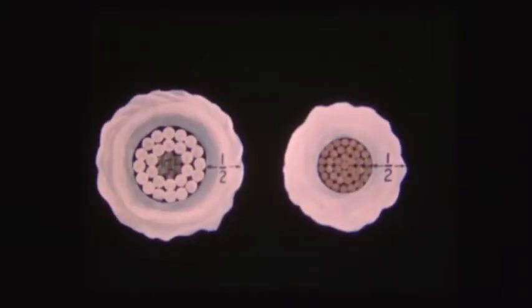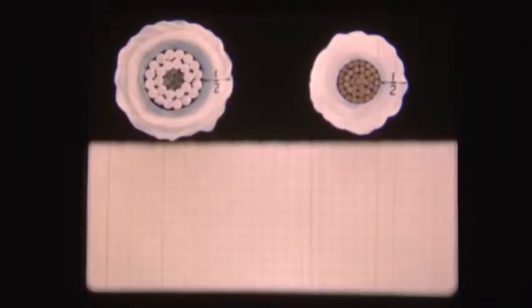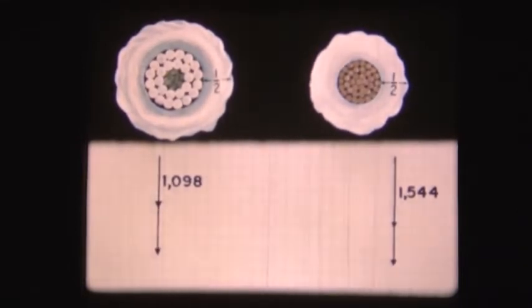Actually, the choice of conductor material isn't quite that simple. We have to consider such things as the added weight of ice, a half-inch coating throughout most of the Pacific Northwest, and up to a full inch or more where winters are unusually severe. Then, there is the added force of wind, which can reach velocities as high as 100 miles per hour in some localities. Let's follow through with the same examples and see how the design engineer uses vector diagrams in making a choice of materials. First, to the weight of a thousand feet of bare conductor, we must add the corresponding weight of a half-inch coating of radial ice, or 1,005 pounds for ACSR and 822 pounds for the equivalent copper.